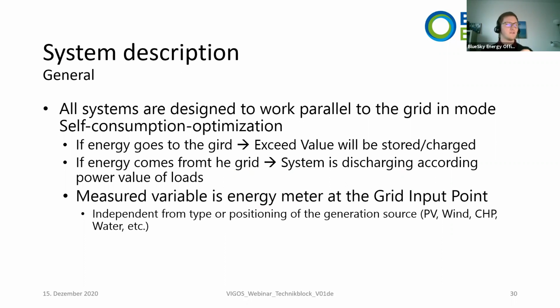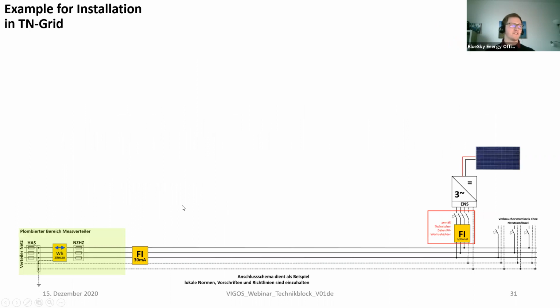So if energy goes to the grid, the exceeding value will be stored or charged inside the battery. And if energy comes from the grid, the system will start discharging according to the power value of the loads. And the measured variable is the energy meter at the grid input point. So I hope we have the same understanding of grid input point. If you look at this schematic here, on the left bottom side, we have the grid input point, where the grid comes in, where the grid connection is.